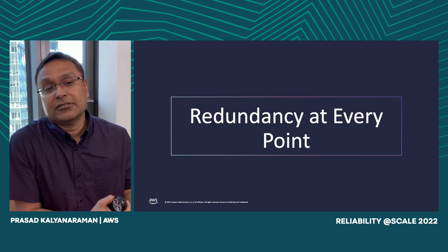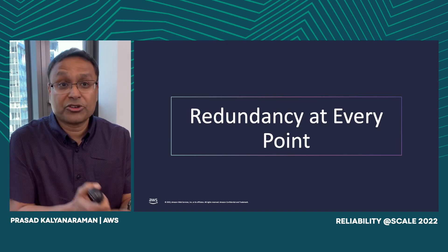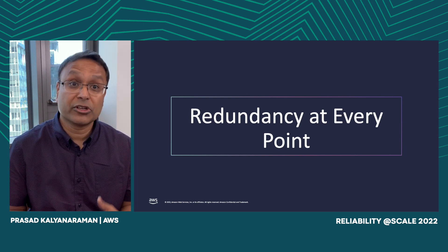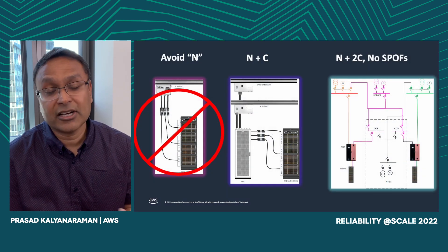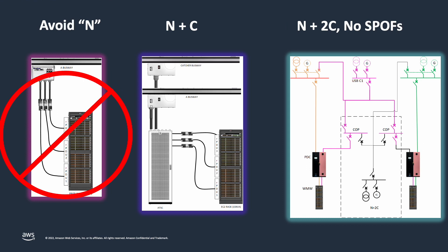In addition to reducing blast radius, the next important thing is going through your single line diagrams to ensure redundancy at every point along the way. We never design our server racks with just N power — N meaning utility backed up by a generator. We don't operate with N power. Our initial designs operated with what we call N plus C, where C stands for catcher — basically another lineup, another utility-plus-generator backup, that's available.